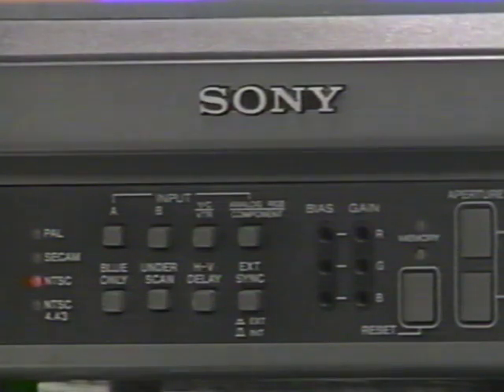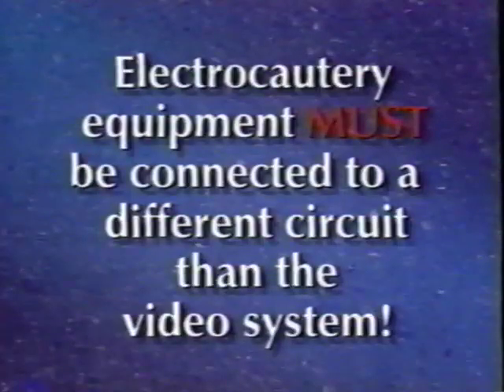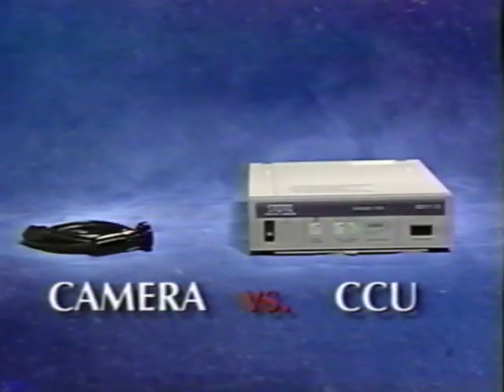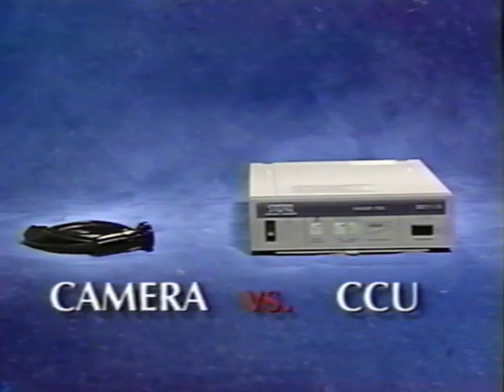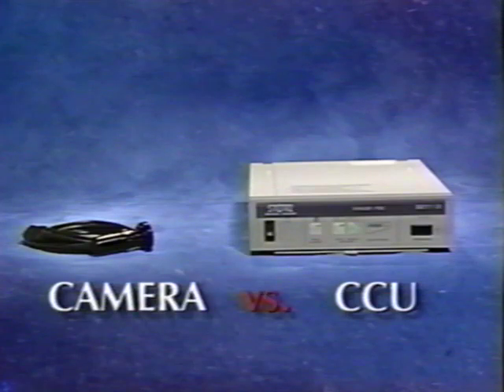The problem of interference may have to do with a short in the camera cable or with the use of electrocautery equipment. Electrocautery equipment must be connected to a different circuit than the video system to prevent interference. High-frequency cords placed too close to the camera cable can also cause interference. If you go through all of the above-mentioned checks and by process of elimination determine that the camera is not functioning properly, then take it a step further to determine whether it is the camera head or the CCU at fault. Although cameras vary somewhat from manufacturer to manufacturer, the following 4 tests will work for all camera types.